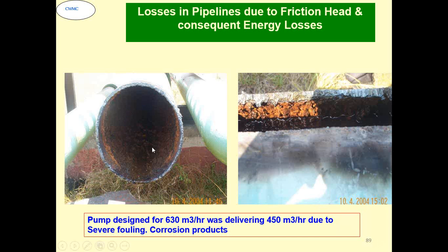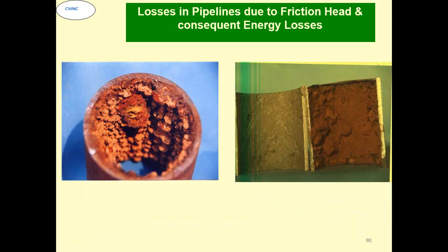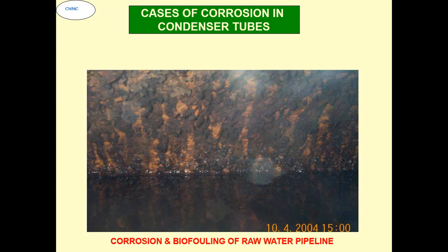Now this pipeline you see here is a main pipeline which is supposed to supply cooling water to a 630 cubic meter pump, but it was not able to deliver more than 450 cubic meters due to severe fouling and corrosion in the pipeline. Ultimately this pipe was replaced by an HDPE pipeline and the problem was resolved. This is the same station. You can see the raw water pipeline also severely biofouled. Some more cases of biofouling: again the raw water pipeline of the same station. We cut the pipe and you can see the biofouling inside. This water was only 10 ppm hardness, 10 ppm alkalinity, but still such severe biofouling.